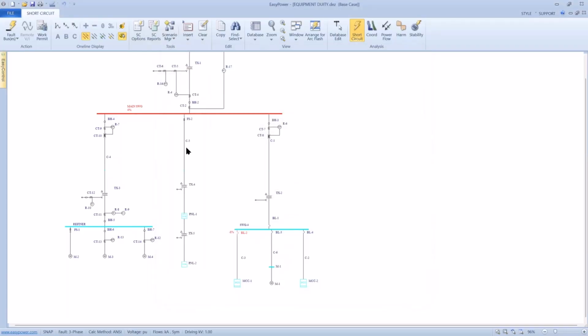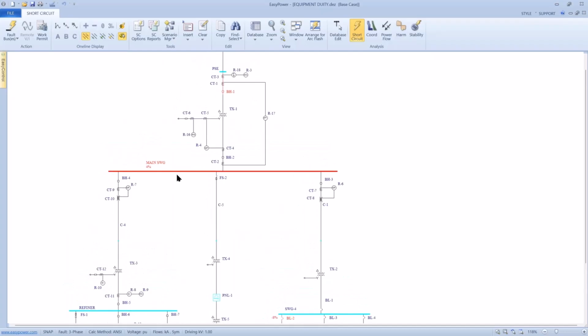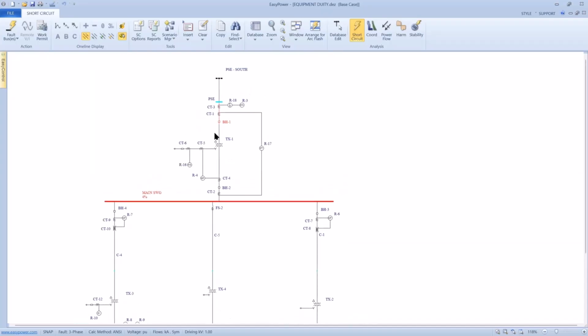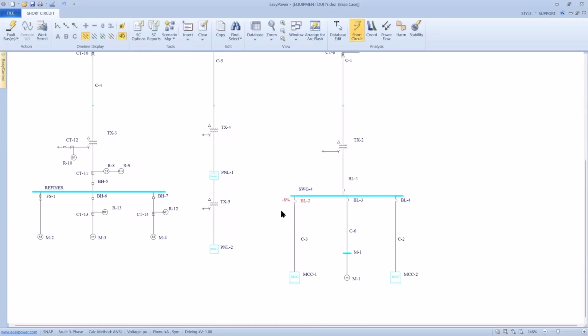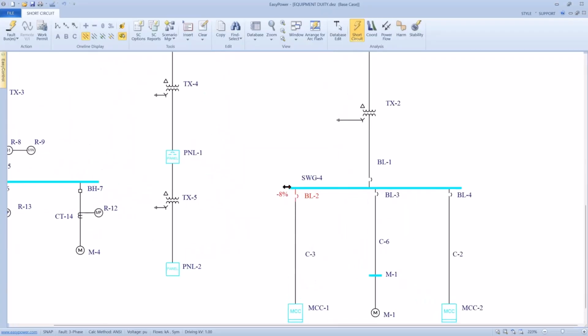And so I've got three cases where I will see a result. I've got a positive number, which means some component on this bus is over-dutied. It won't meet the manufacturer's spec, or rather the current it's rated for is lower than it will see at a worst case fault. I can see red numbers with nothing there, which means I didn't properly set up this breaker because it doesn't result in this threshold test. And then I can see a red indication with a negative number, which means it's inside that 10% threshold, but it's still compliant.